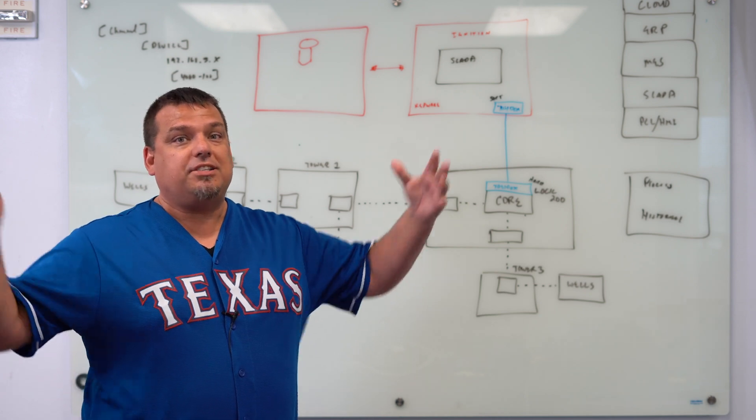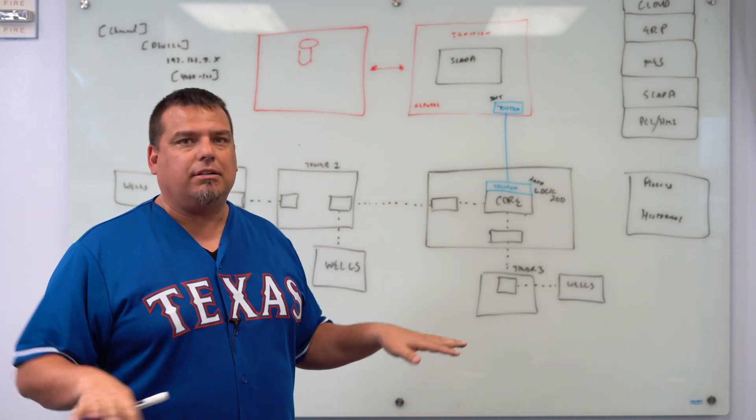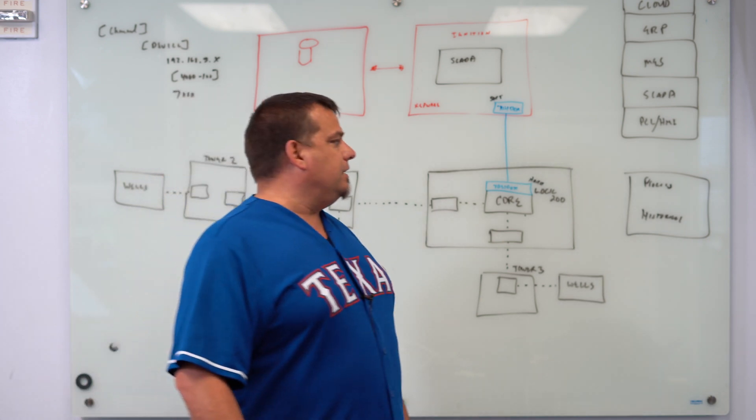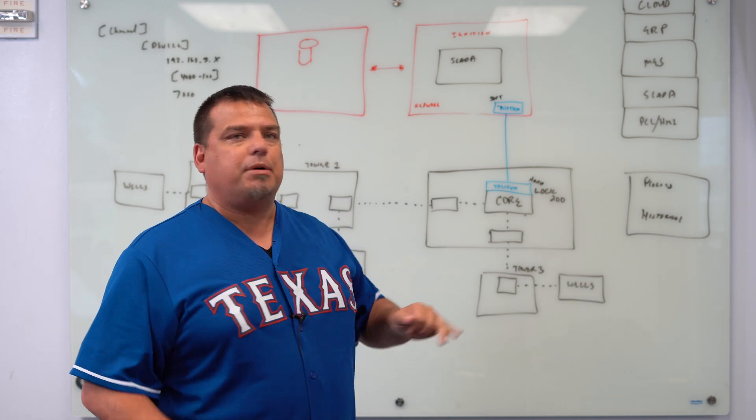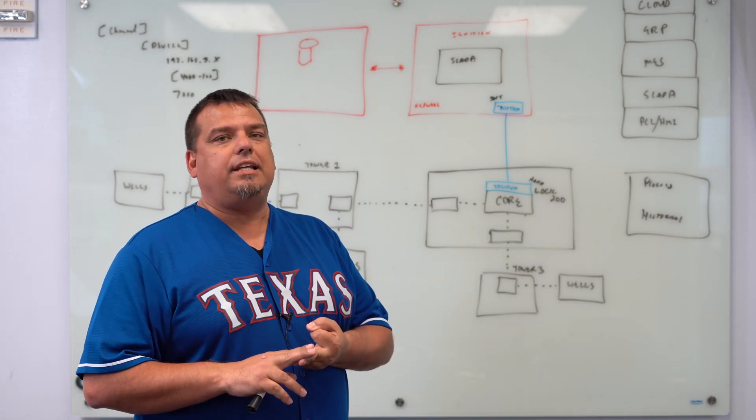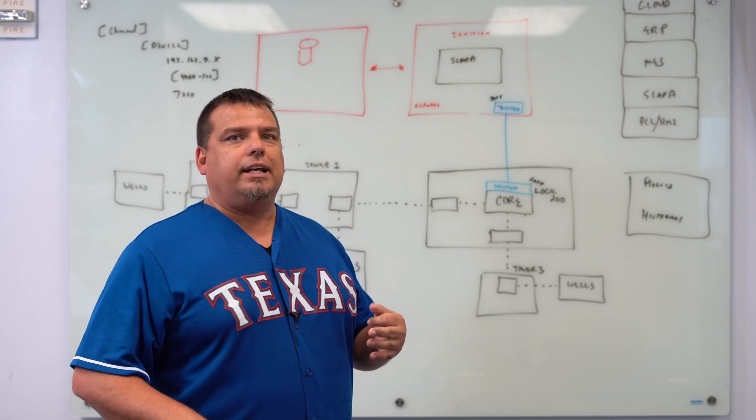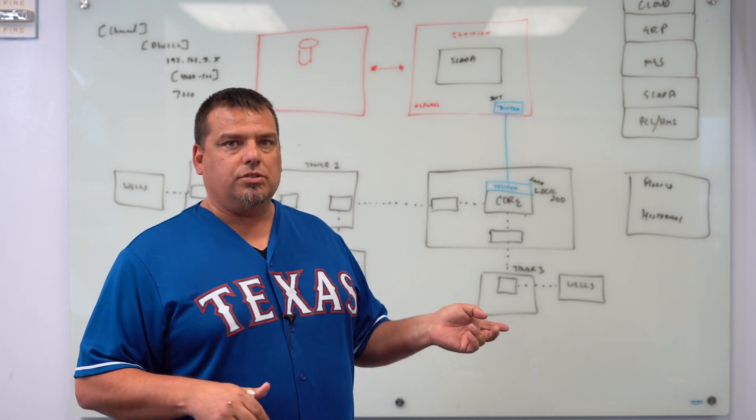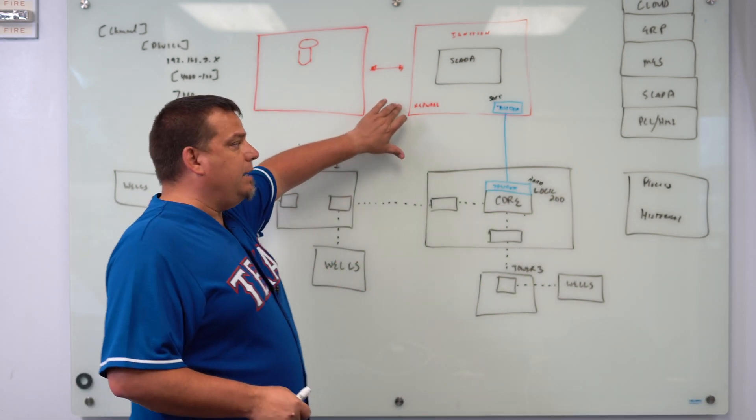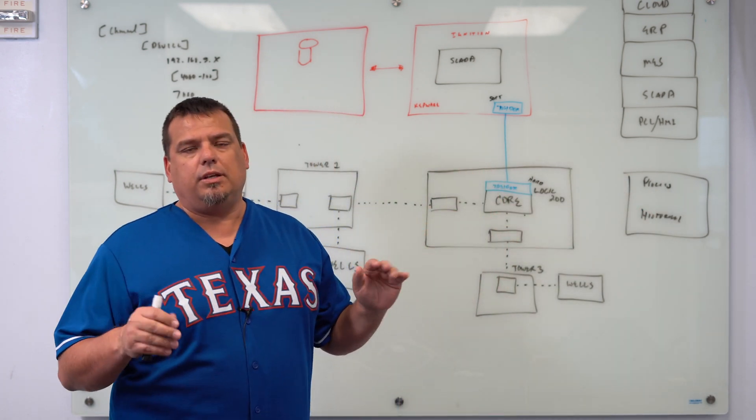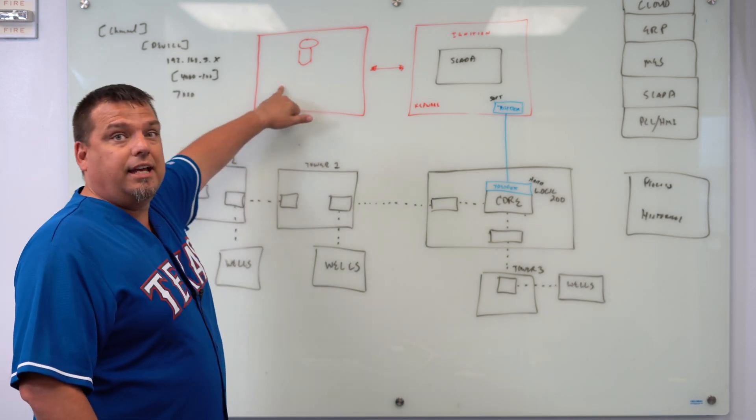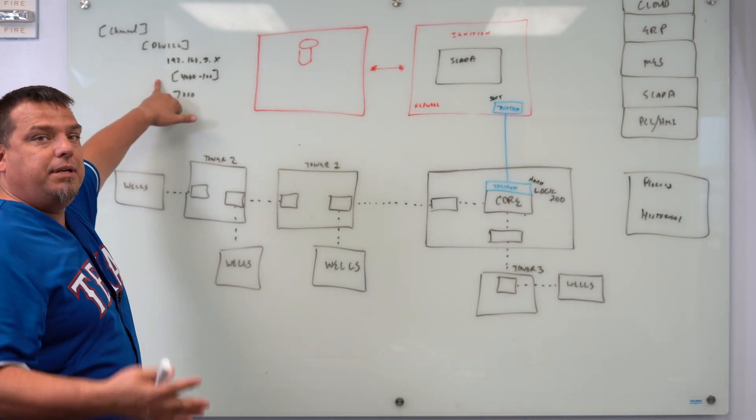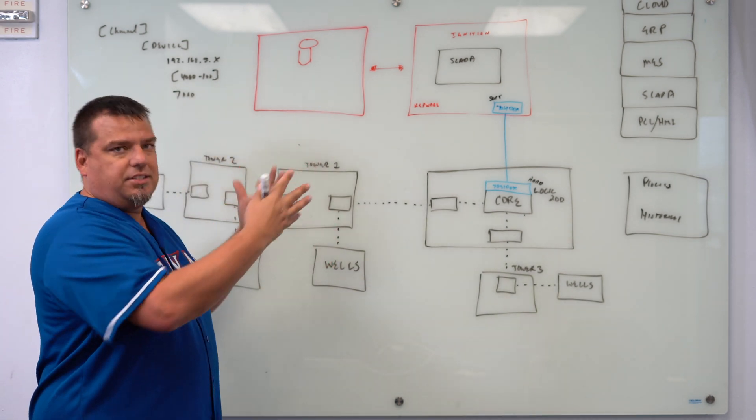A shut-in well is basically leave the valve closed, don't run anything, let somebody go out and fix it and don't have the well explode. It's called shutting in the well. We store alarm data, event data. Every time a program is changed, there's an event record stored. We store hourly data. Every minute of the hour, we're storing how much flow, what the pressures were, all that kind of stuff. Then we also have daily totals. Using Kepware's EFM suite, we are able to export all of those records. We can send them lots of places. We send them into a SQL database. Then what we can do is go look up any of the meters by meter ID and grab back those records and trend the data inside the SCADA system.